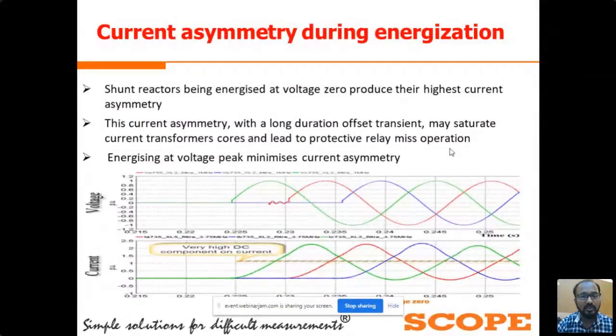The other main issue with the shunt reactor during random closing is that whenever the shunt reactor is energized at voltage zero, that produces the highest current asymmetry. In this waveform we can see that if we close the shunt reactor at the voltage zero moment, it will produce a high DC asymmetry. This means the current starts on the positive side only or on the negative side only, and after a few milliseconds the sinusoidal current will go normally.